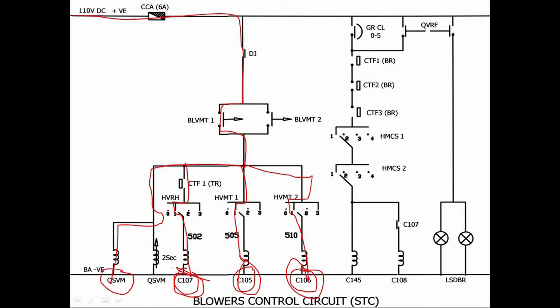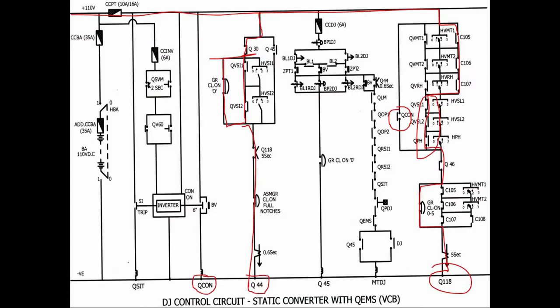So since 110 volt supply is given to these branches, they will energize and the contactors will close. At the same time, since QSVM is energized, the QSVM normally closed interlock is opened here. Now the static converter does not get supply, and the static converter stops functioning. So here we can say after closing BLVMT, QSVM is energized, thus the static converter stopped functioning. Meanwhile, C105, C106, C107 contactors are closed, and now in the auxiliary power circuit the contactors are closed and the path is kept ready for the blower motors also.